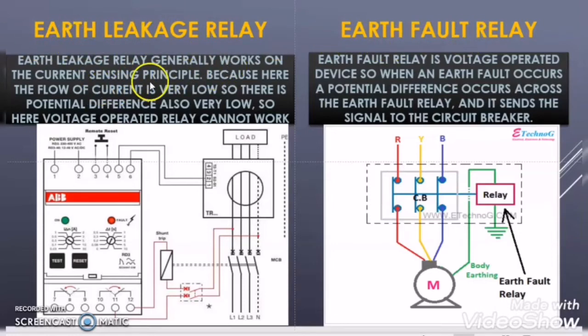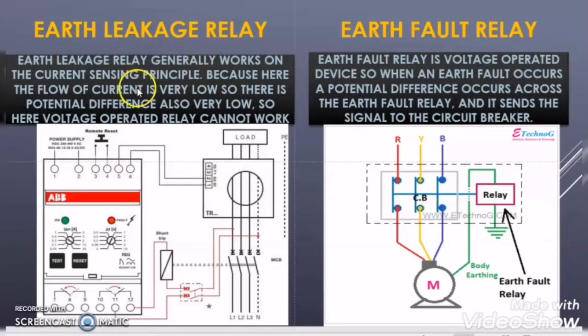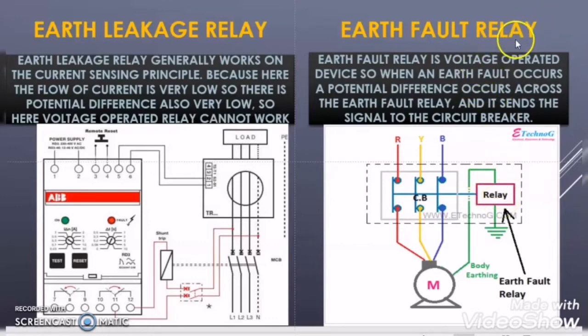The earth leakage relay is a current-operated device. Since it deals with very minute current, it senses a very small current difference in the phases and trips the circuit using that current imbalance. But in the earth fault relay, there is a huge current flowing during the fault, so the voltage induced in the tripping coil is very high. Therefore the earth fault relay uses a voltage-induced technique to trip the circuit — it is basically a voltage-operated device.